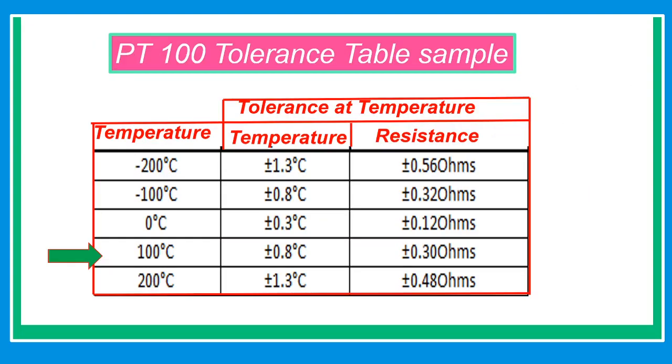This is the common table for tolerance of PT100 for class A and B. Example, at 100 degrees Celsius, the tolerance is 0.8 degrees Celsius or 0.30 ohms. But if you are going to measure 200 degrees Celsius from 0.8 degrees Celsius, it will increase to 1.3 degrees Celsius or 0.48 ohms.